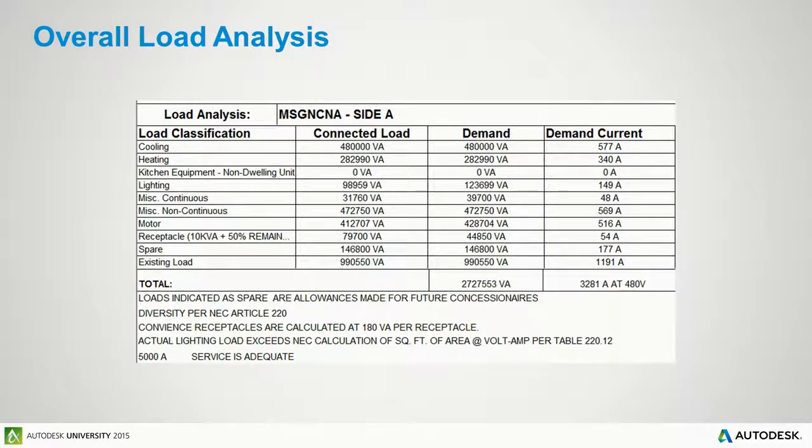And so for our switchgear, we don't typically publish a panel schedule. Our one line holds all the data for the switchgear, or whatever you're using as your service entrance. You're going to have your one line, and then once you get downstream of that is where you start publishing panel schedules. So here, I've got a panel schedule called load analysis that I formatted in this way, and then you just delete all of the upper information, all the circuits, all the panels, all that information at the very top, and I'm just left with the load analysis.